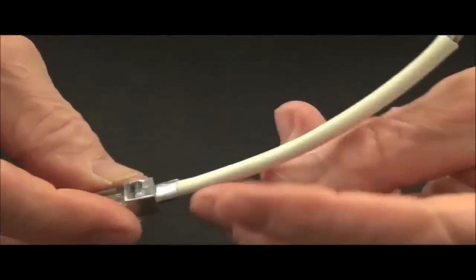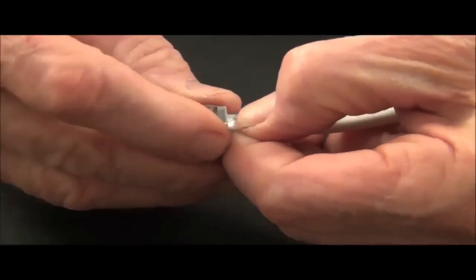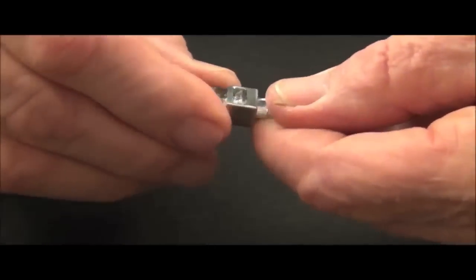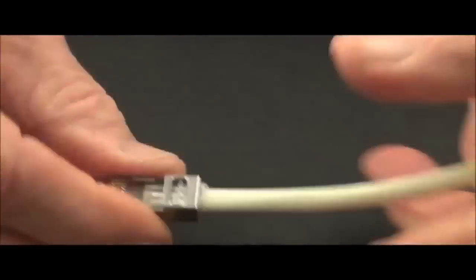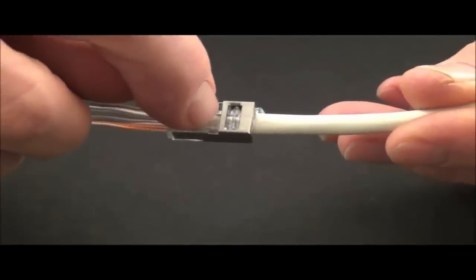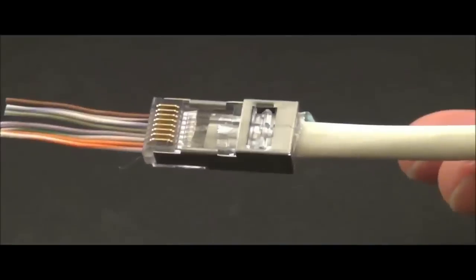I'm putting my cable, connectors are coming out the front end. The shield's at the back end, so only about three eighths of an inch down on the jacket from the end. Stop at that point and I'm ready to do my crimp. You'll notice I've set my jacket even further than it needs to be. The closer the twist to the point of termination, the higher the performance.